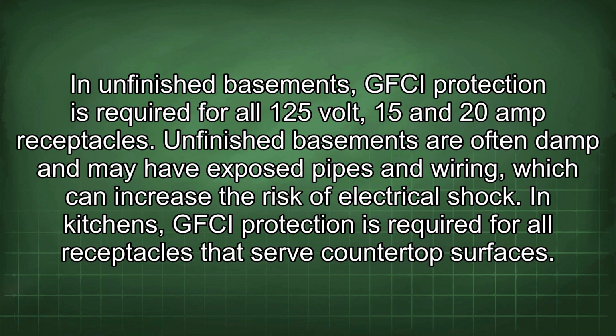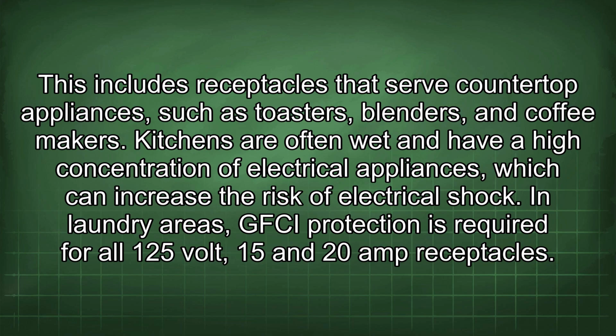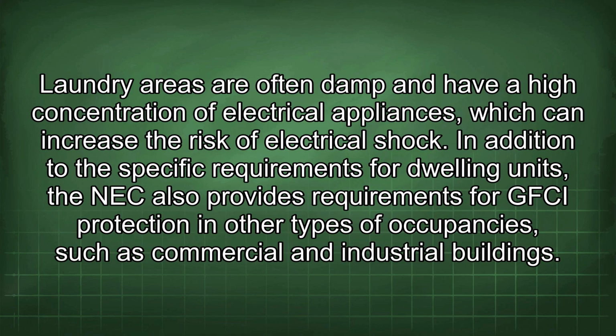In kitchens, GFCI protection is required for all receptacles that serve countertop surfaces. This includes receptacles that serve countertop appliances, such as toasters, blenders, and coffee makers. Kitchens are often wet and have a high concentration of electrical appliances, which can increase the risk of electrical shock. In laundry areas, GFCI protection is required for all 125-volt, 15 and 20 amp receptacles. Laundry areas are often damp and have a high concentration of electrical appliances, which can increase the risk of electrical shock.